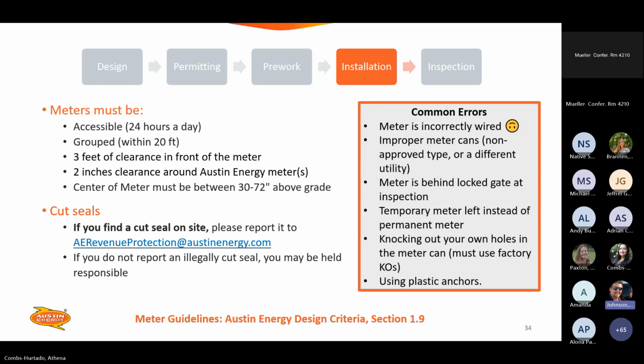Improper meter cans, not an approved type or a different utility. So I had one recently that they had an approved meter base from our meter base website, but looking a little closer into it, it was approved for 120/208 volt and 480. It was actually a commercial meter they were trying to use on a residential project, and I had to decline that. They cannot use that meter for this residential project. And I showed them where on the website the differences between the two were. They changed the meter base out, meter is now installed, project finished. So just make sure you look through that website before you buy that meter base, that it is the appropriate kind for that particular work you're doing.